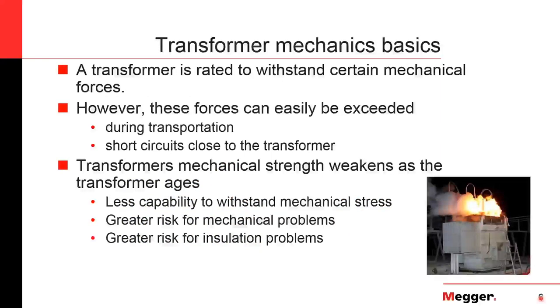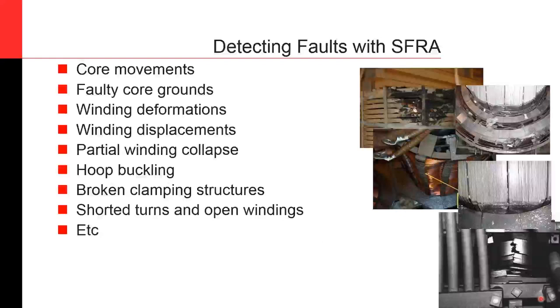Why do we test transformers? The transformer itself is designed to withstand certain mechanical forces. But during certain parts of its life — like early on during transportation — some of these forces can be exceeded. Or if there's a short circuit and the windings expand and contract too quickly, you can have mechanical deviations. As the mechanical strength weakens over time, you have less capability to withstand further mechanical stresses and a greater risk for insulation problems as well.